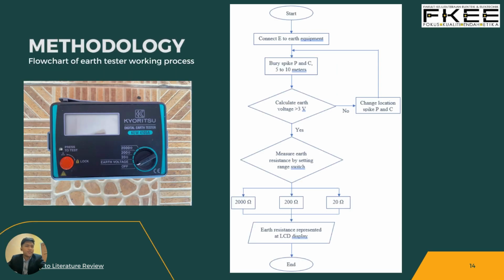Next in methodology, I'll talk about the flowchart of the earth tester working process, which shows how to handle the earth tester machine. First, we need to connect E, the earth electrode. Then we bury the spikes P and C, where P is the potential electrode and C is the current electrode, spaced between 5 to 10 meters apart.